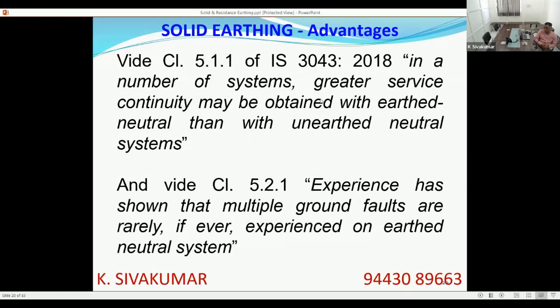Whereas in a solidly earthed system, by perfectly doing coordination, only the faulted portion is affected, only the faulted zone is isolated, and healthy portions are not affected. Since current detection is possible here, you can always provide a current transformer and a protection relay, an earth fault relay. You can always isolate only the faulty portion. The healthy portions can remain in service, so service continuity can be guaranteed.